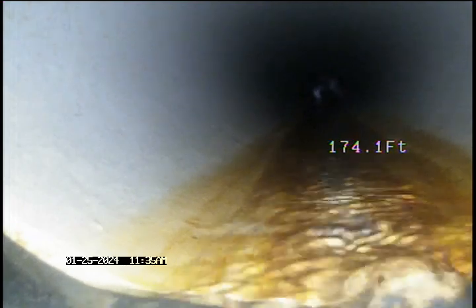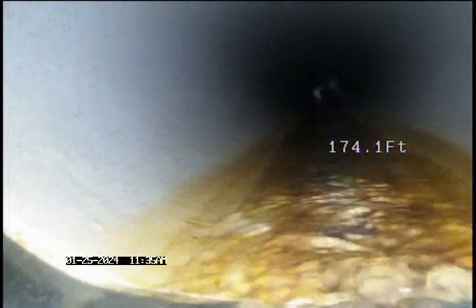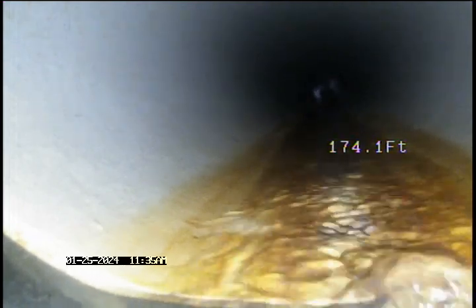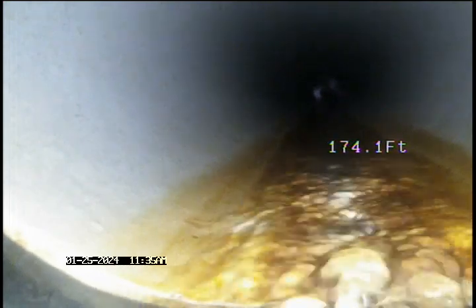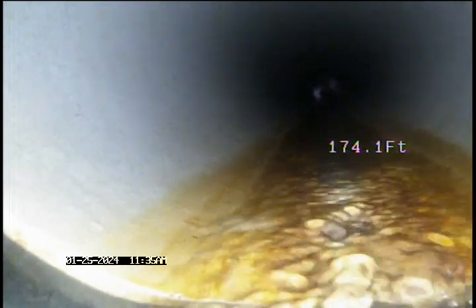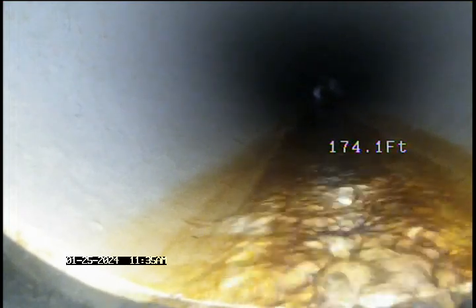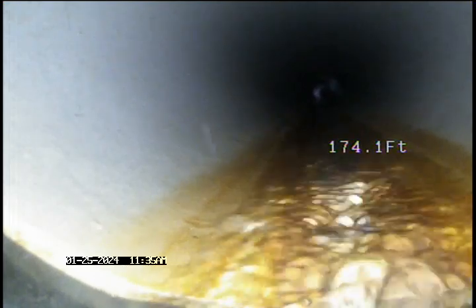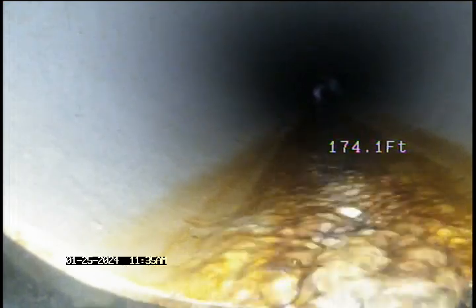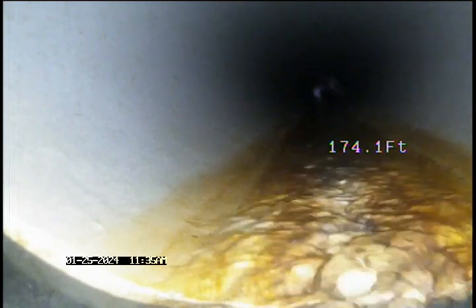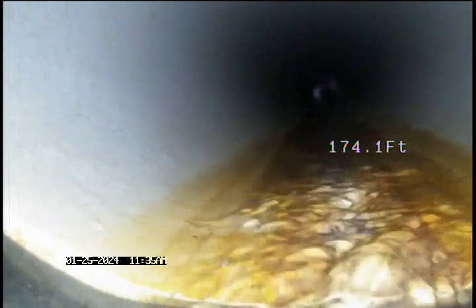Counter's at 174 feet. This is as far as we can push due to resistance with some turns in the pipe and some ice that's present that we will see. This position has been located in the grass on the southwest corner of this part of the building, marked with flag and paint. Depth says about 6 foot 10 inch at this point.